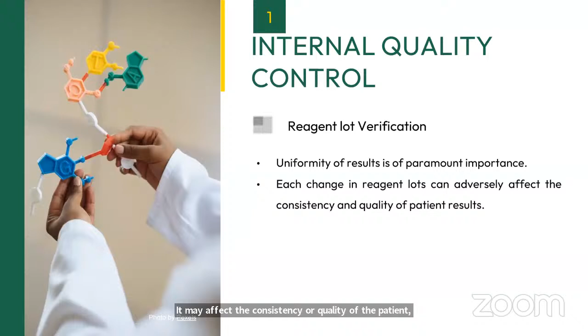So uniformity of the result is of paramount importance. Each change in the reagent lot can adversely affect the consistency and quality of the patient result. So whenever there are changes in the lot, it may affect the consistency or quality of the patient result. It is not that those lots are defective, but to verify that your results are as per the specifications, you should perform the lot verification.